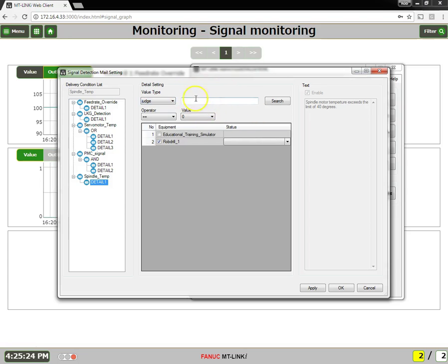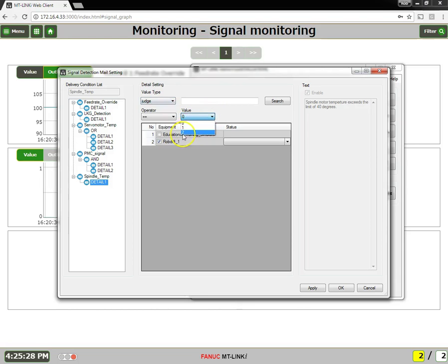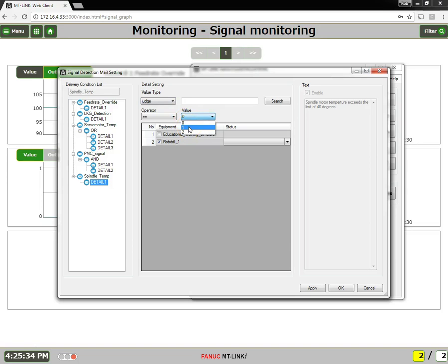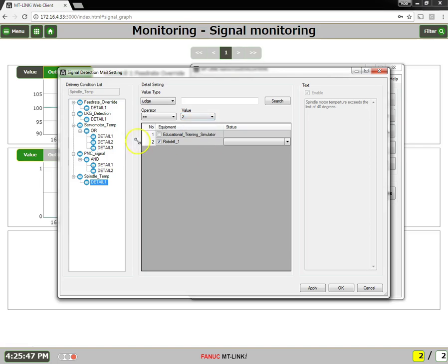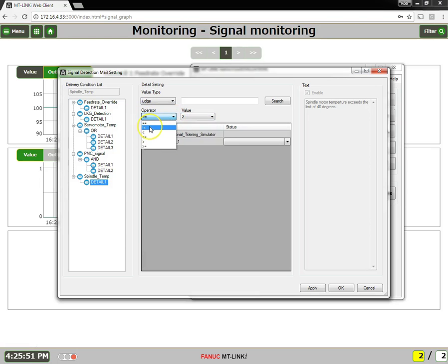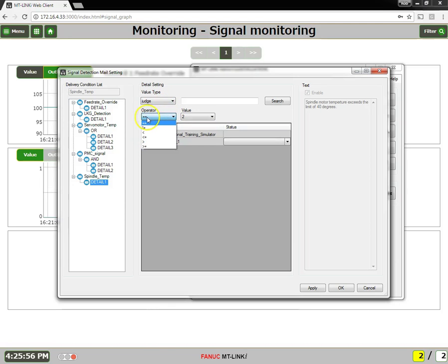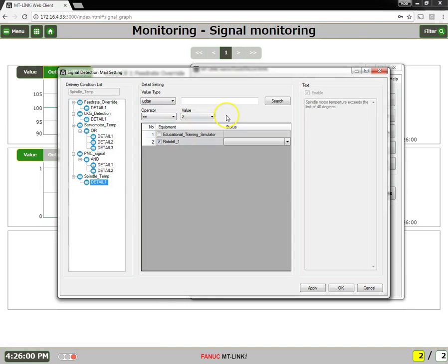The values that you can use in judge is 0, 1, and 2. 0 means normal condition. 1 is where I set my warning threshold. And 2 is where I set my error threshold. And in my case, I have set it up for 40. So I'll select 2. And so the operator, you can choose equals, not equals, less than, greater than, so on and so forth. So I'm going to say equals to 2. So when the signal equals my error limit, that's my trigger.